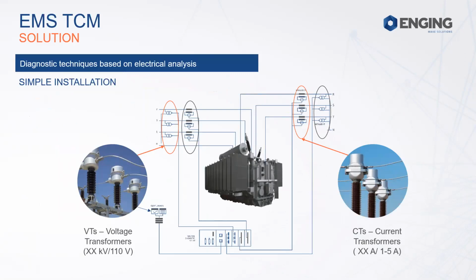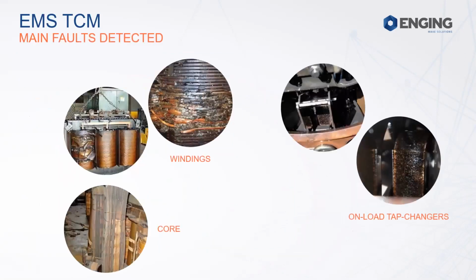We take the voltage and the currents of the transformer, as you can see, in a completely non-invasive way, independently of the kind of transformer we are talking about. So what are we able to detect? Well, basically, we are able to detect the main faults of a transformer. In this case, we're able to detect the faults in the core, in the windings, and in the on-load tap changers.